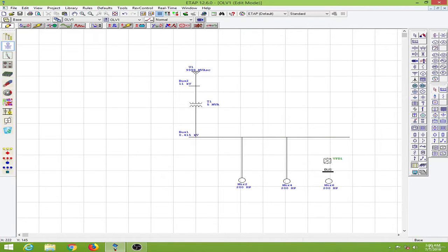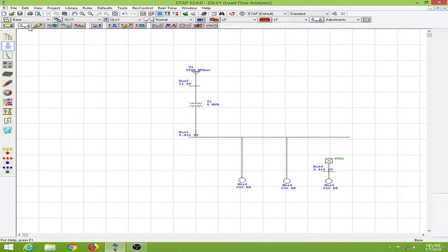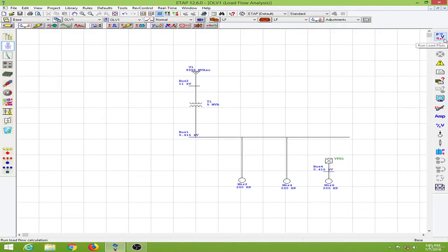I will add a bus over here. In order to provide the ratings for the variable frequency drive I will have to obtain the data from the load flow, so let us conduct a load flow.